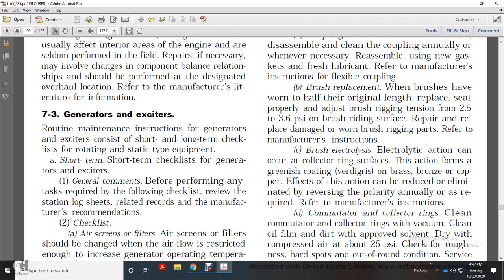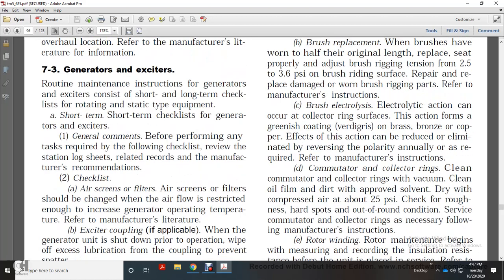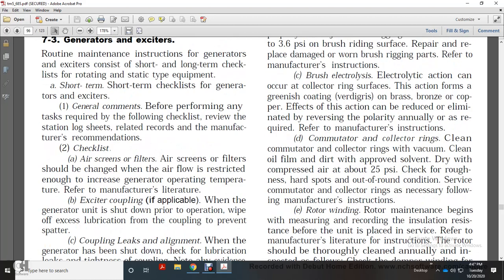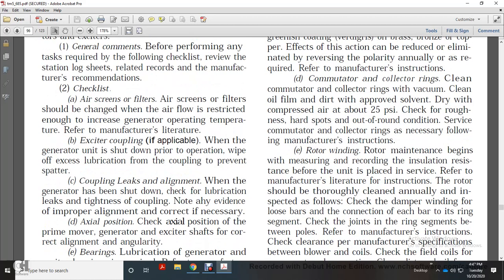Alright, your brush electrolytic action can occur at collector ring surfaces. This action forms a greenish coating (verdigris) on the brass, bronze, or copper. Effects with the action are reduced or eliminated by reversing polarity annually as required, referring to manufacturer instruction. Commutator and collector rings: vacuum clean, oil film and dirt with approved solvent and dry with the compressed air at 25 psi. Check for roughness, hard spots, and out-of-round conditions. Service the commutator and collector rings as necessary per the manufacturer instruction.